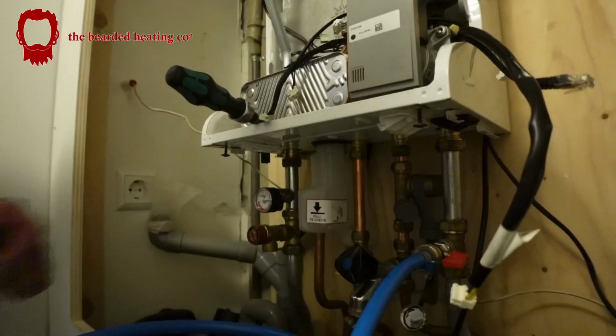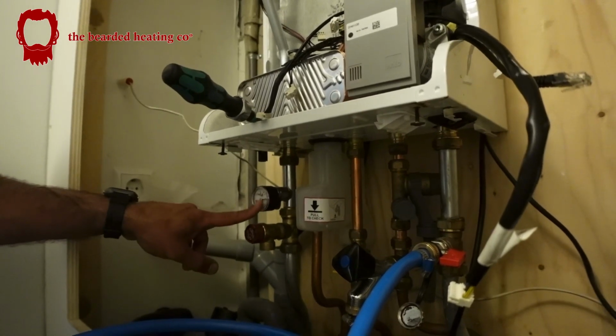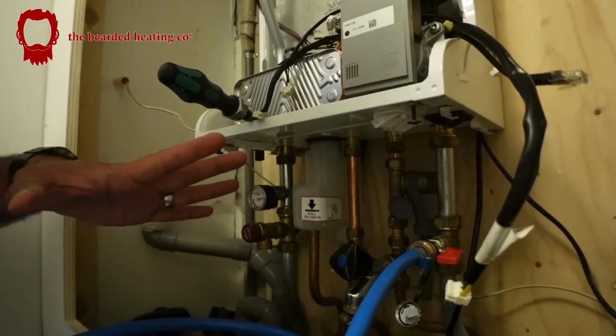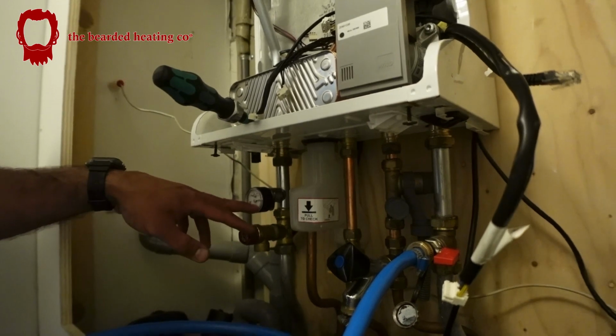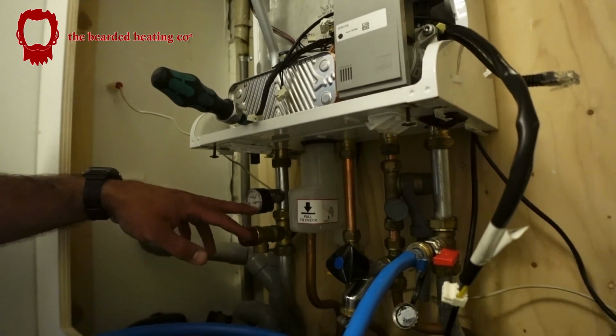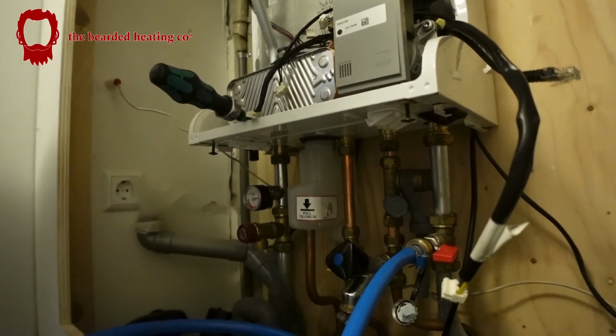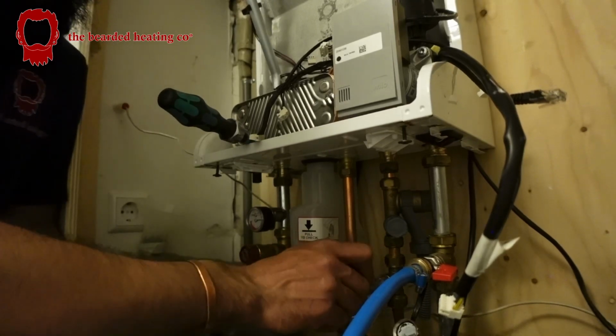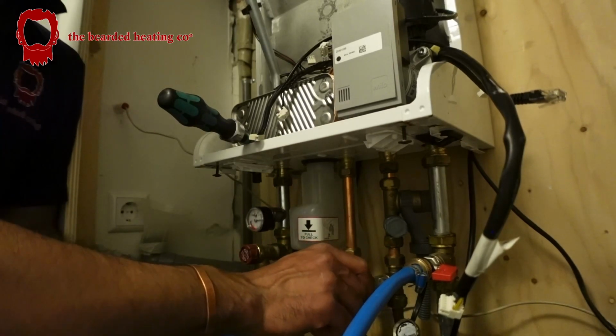That's it, they're clean. The nice thing about this boiler is that there's a pressure gauge on it, an analog one, so I don't need to power the boiler up. I'll just fill it up to about 1.5 bar, test for leaks, and then flush the heat exchanger. Right, that's connected, and there we go.